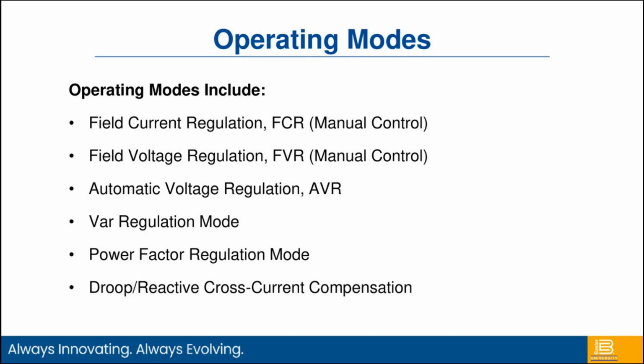And if I'm paralleling multiple machines, I am going to want to make sure that they're sharing load correctly as they're paralleled. So I want to make sure that each machine is doing its equal contribution to supply the reactive component to that particular load. So I can do this in multiple ways. We can do this in droop control, and we can do this in reactive cross-current compensation, or some people call it reactive differential compensation. That's just like tying all my CTs in a kind of a loop, which will end up balancing themselves out and make sure that each machine is sharing properly.